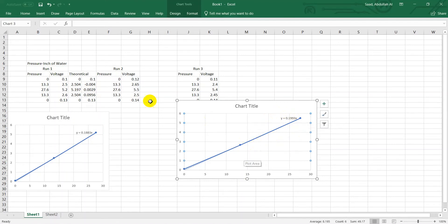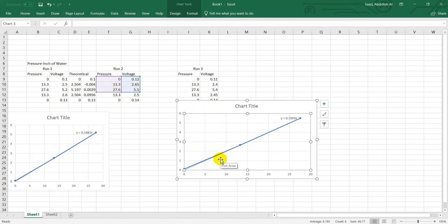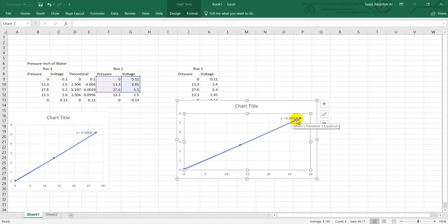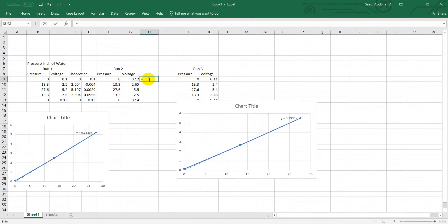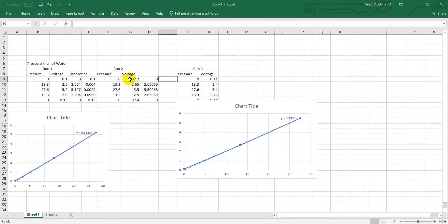The coefficient of x — 0.1993 — is the slope, and this is basically the sensitivity of the sensor. You might wonder why we choose only the first three data points. If we choose all five, that will not be a single line — there would be two lines, and you cannot find a single slope. That's why we work with only the upward data to find the relation between voltage and pressure, and we apply that relation: pressure times 0.1993 gives the theoretical value.